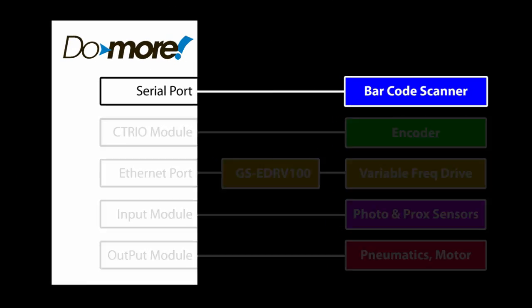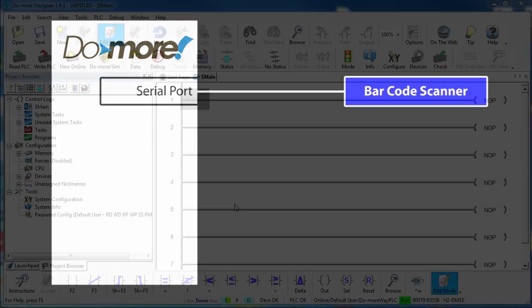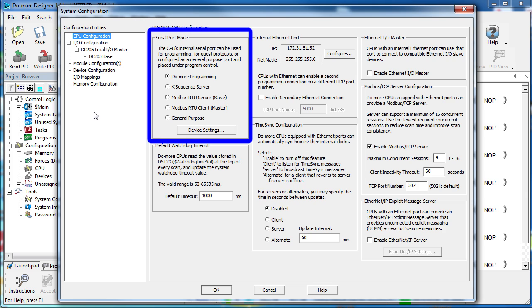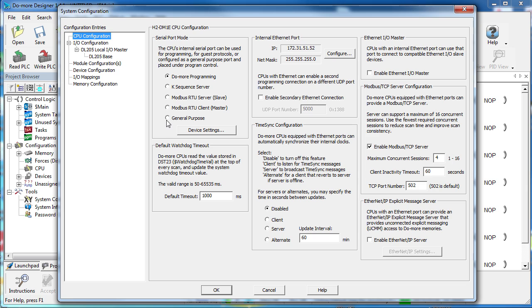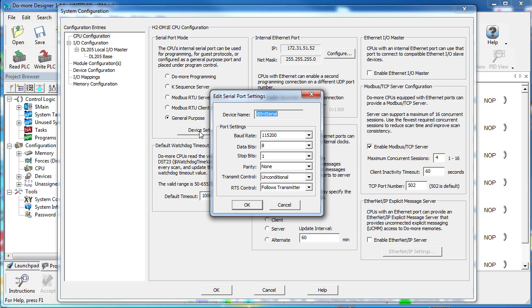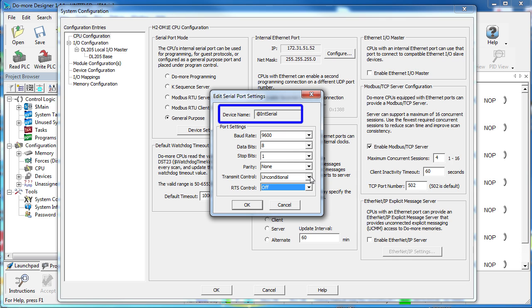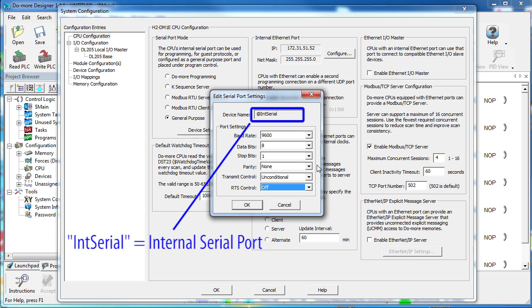Let's start with the barcode reader on the serial port. In the CPU configuration we see that the serial port device already exists, so we just choose how we want it to behave. Our barcode reader just sends out ASCII text so we'll use this as a general purpose serial port and configure the COM port parameters to match those of the barcode reader. You can see the default name of the serial port device starts with the AT sign. All devices default to that so you know that Do-more thinks it's a device. This says it's the internal serial port device.